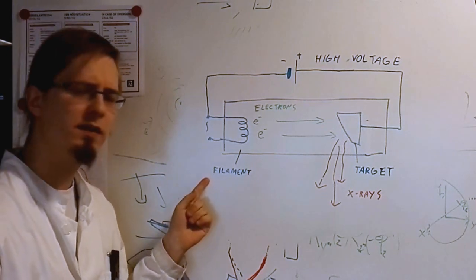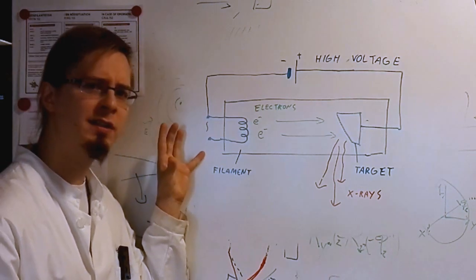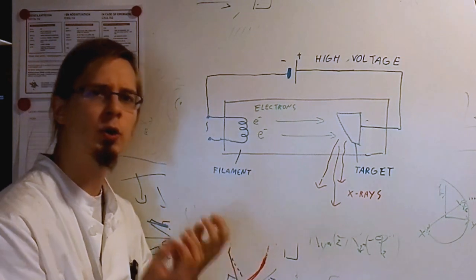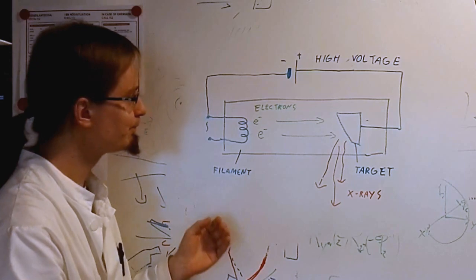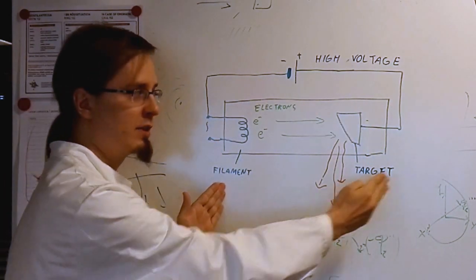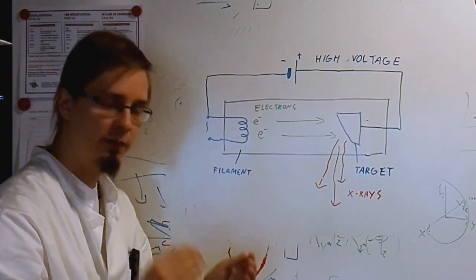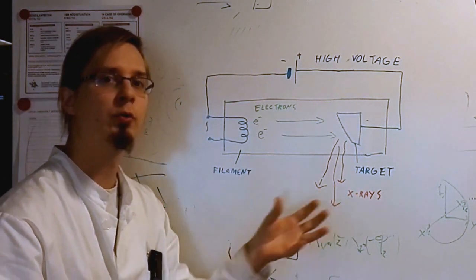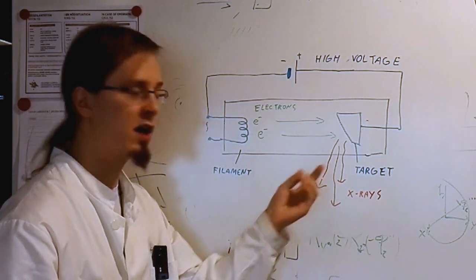So the filament is basically a light bulb. The filament is heated up with a low voltage current, and that heating causes the electrons to be released in the vacuum of the tube. The high voltage connected between the filament and the target accelerates the electrons to very high velocities, and when they hit the target, they produce x-rays when they decelerate and excite the atoms of the target material.